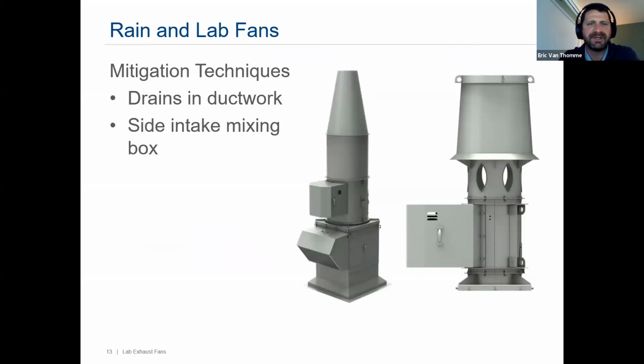I want to pause here just briefly to talk about rain and lab fans. There are a couple of things that really need to be taken into consideration when utilizing lab exhaust fans, especially this inline style. There are some housed centrifugal style lab fans that can mitigate rain a little bit differently, but specifically with these inline styles, these are all open air. There's no damper on the outlet of the fan that's going to shut off 100% of the rain coming into the fan. Because of that, rain can actually make its way down through the fan, especially when it's shut off for maintenance or replacement, or if you have an N+1, which we'll talk about, redundancy, in a second here.